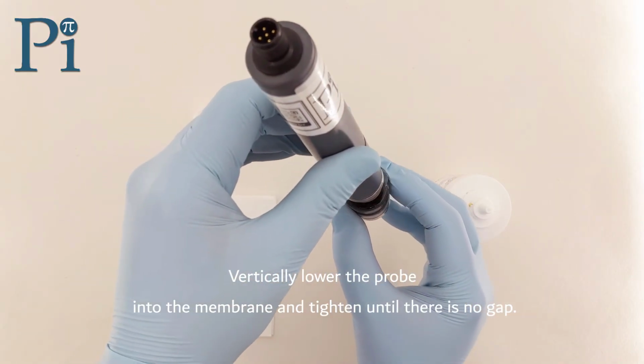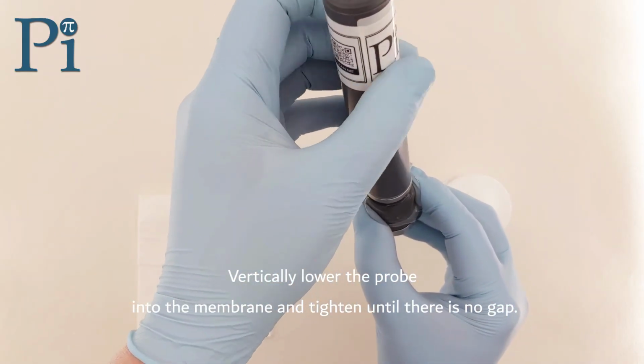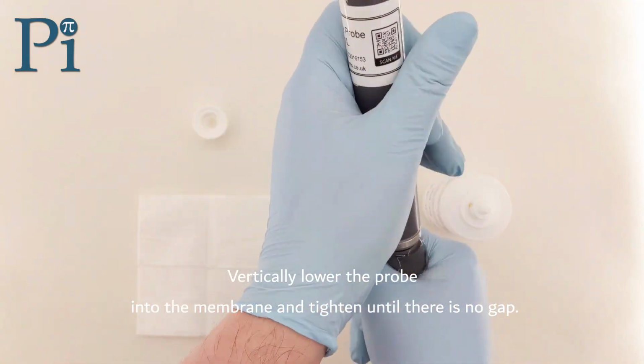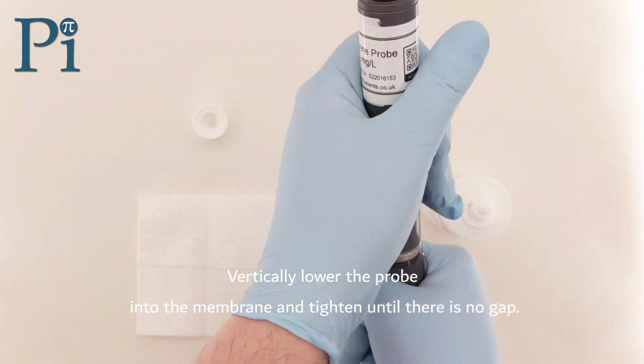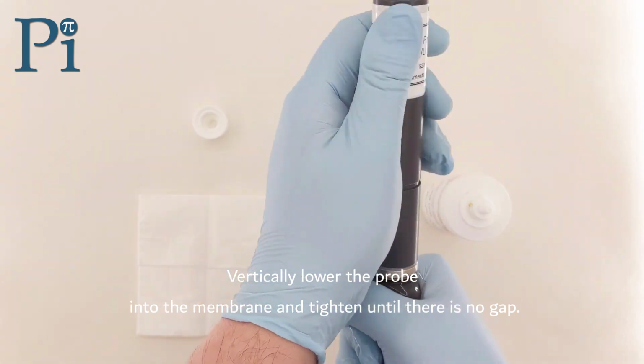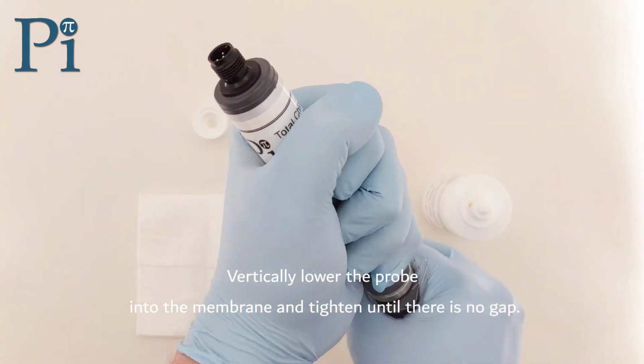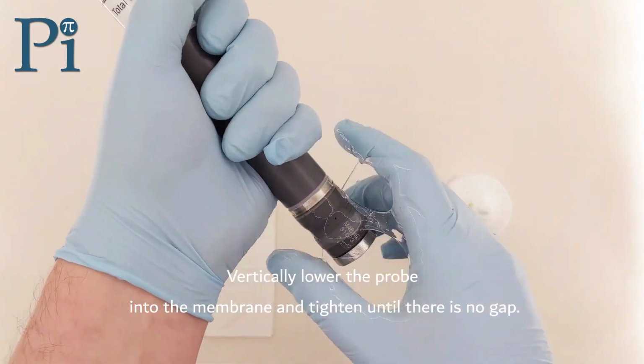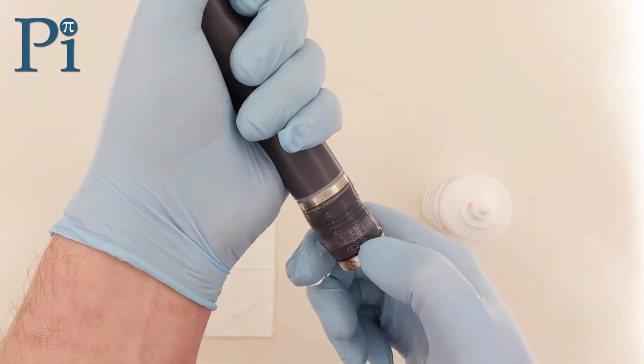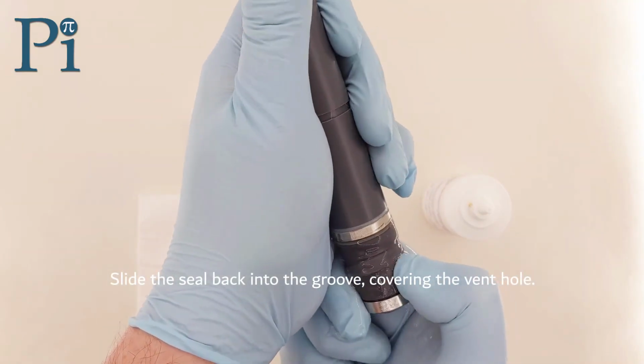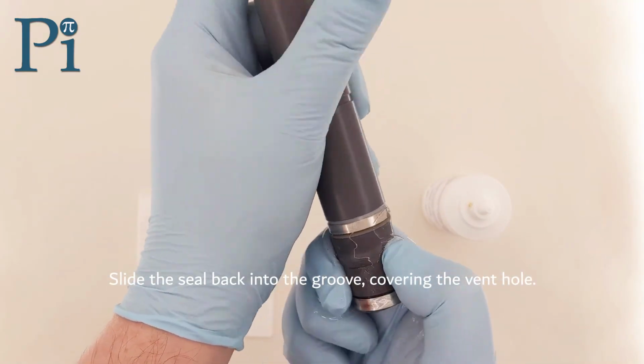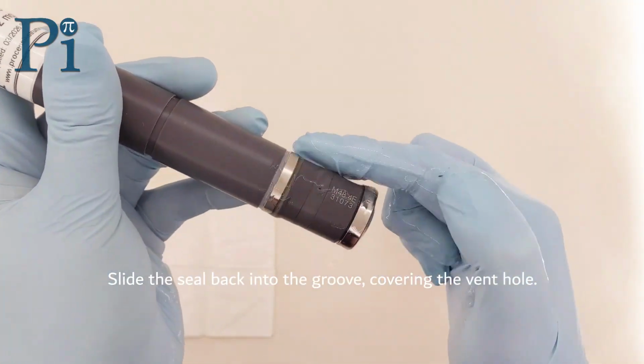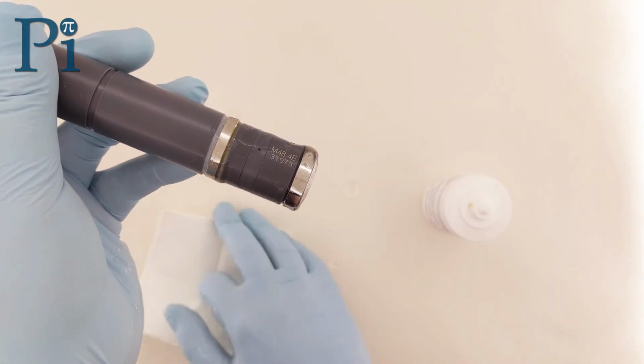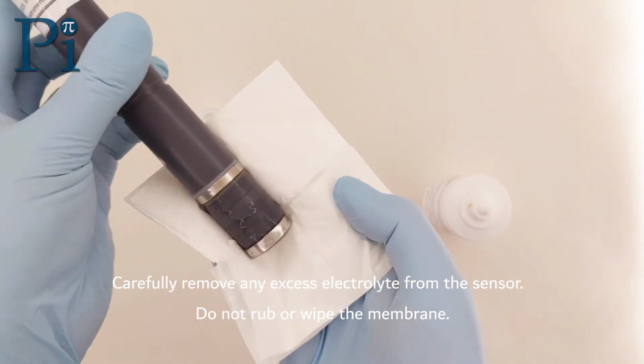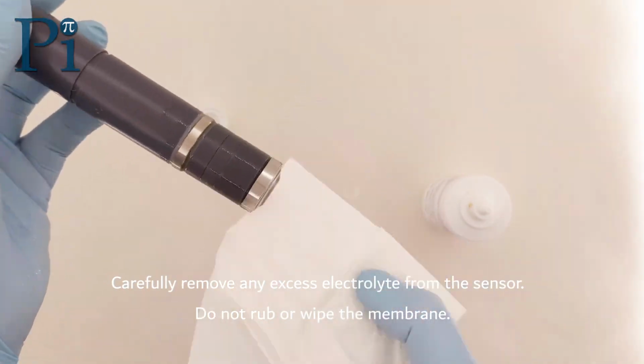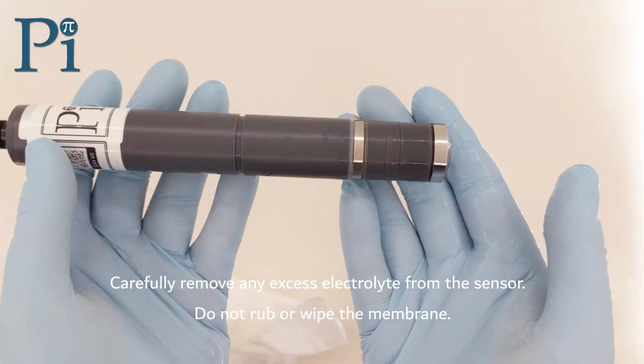Vertically lower the probe into the membrane and tighten until there is no gap. Slide the seal back into the groove, covering the vent hole. Carefully remove any excess electrolyte from the sensor. Do not rub or wipe the membrane.